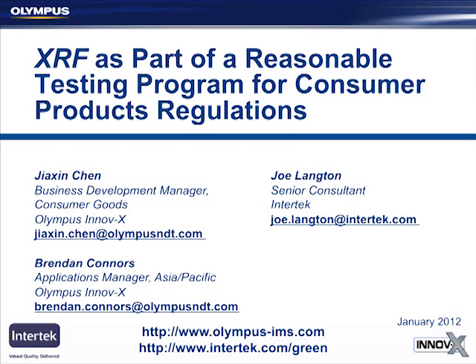In our experience, of the ones that are out there, generally gold anode or tantalum anode work very well because there's very little interference from those elements on any of the elements that you're testing as part of consumer products regulation. Silver anode, you do have a little bit of overlap with some cadmium lines, and if you do a direct comparison, you may find that the gold anode would do a little better than silver anode. You may find the same for rhodium anode, that a gold anode would do a little bit better, but it depends on a lot of features, not just the anode type.